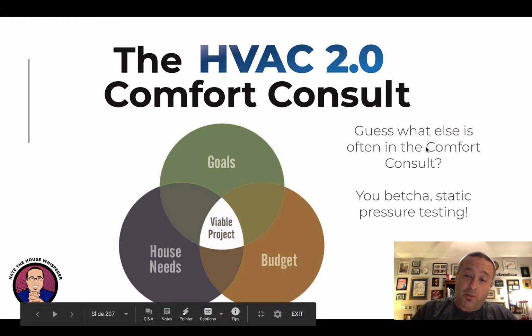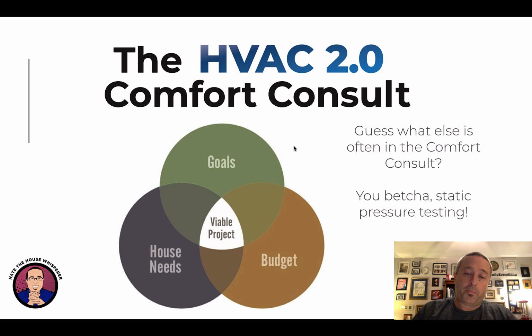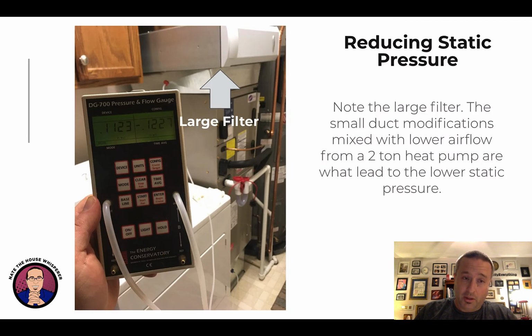So guess what else is in the Comfort Consult? You betcha, static pressure testing. It's not always in there, we don't require it, but it is part of it, and generally we listen to the system, because oftentimes the ductwork can oil can - you'll turn the air handler on and hear thump thump, and watch the ductwork actually expand with the high pressure in them. If that's the case, I go get my drill, we're going to test this. It only takes 10 or 15 minutes to run, so it's not a huge deal, but the Comfort Consult's already pretty long, 3 or 4 hours as it is. But it's an important thing to ask about, particularly in electrification.